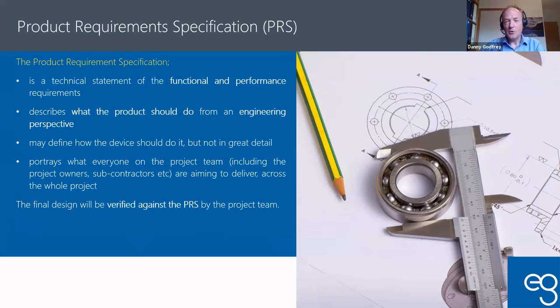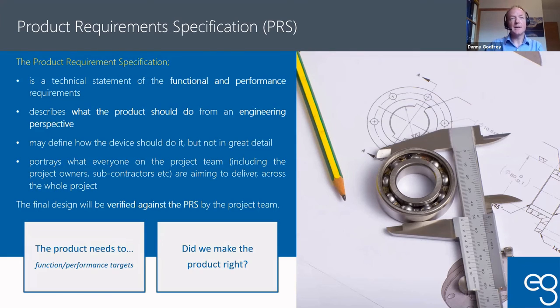It talks about the functional and performance requirements. So the user need we talked about earlier on, it must be heavy enough that somebody can't just put it in their bag and walk off with it. That's a perfectly acceptable user need. But an engineer won't necessarily know whether that means 1 kilo, 5 kilos, 15 kilos. So you need to start putting numbers on things. So the product needs to weigh between 5 and 15 kilos, have a mass of between 5 and 15 kilos.